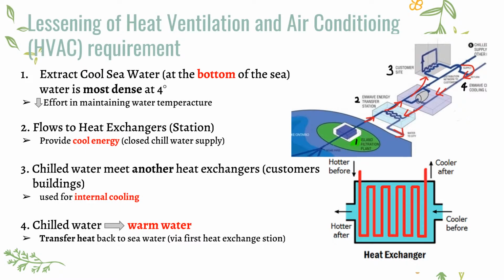In terms of procedures, it is based on the diagram on the top right. Firstly, the seawater is extracted at the bottom of the sea, meaning the extracted water is very dense. One interesting property of water is that it is most dense at 4 degrees. Therefore the extracted water is always steady at around 4 degrees, minimizing the effort needed to maintain water temperature. Secondly, the cool water flows to heat exchangers at a station and is used to cool the water in the closed chilled water supply.